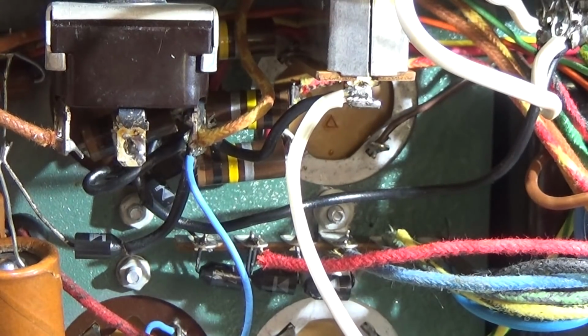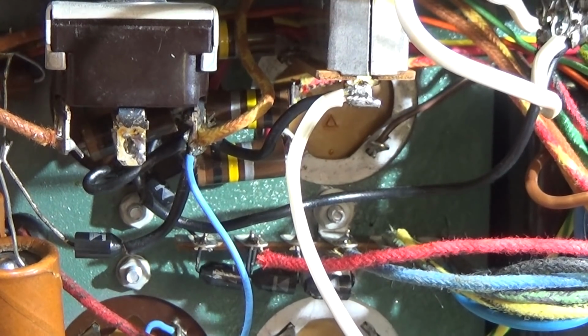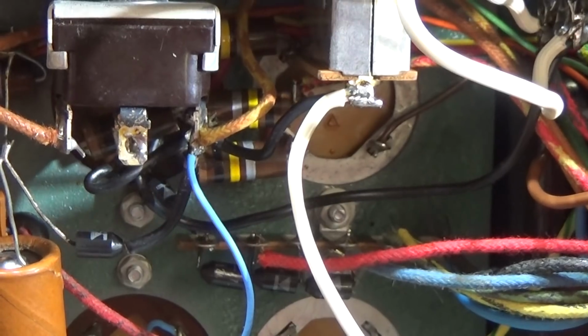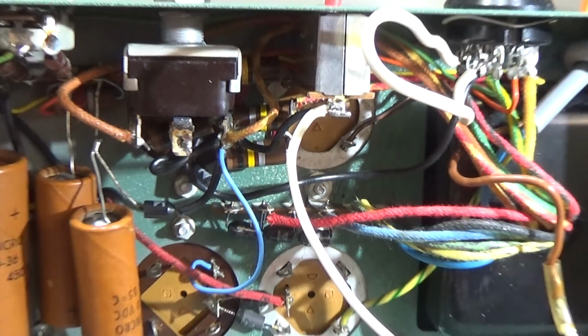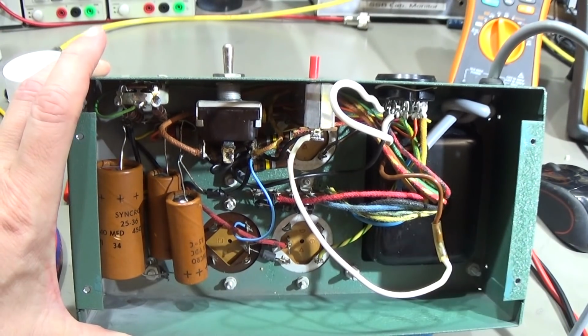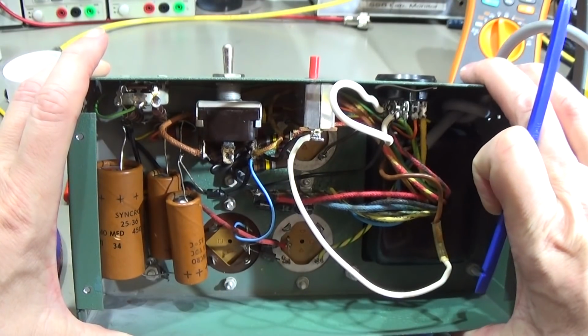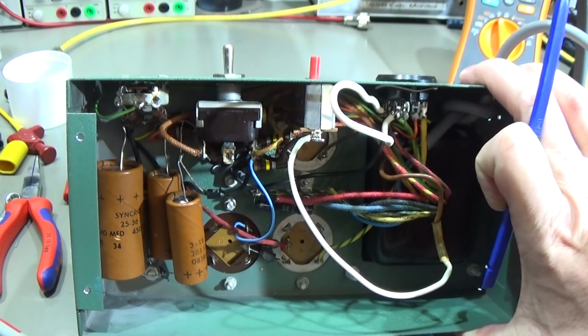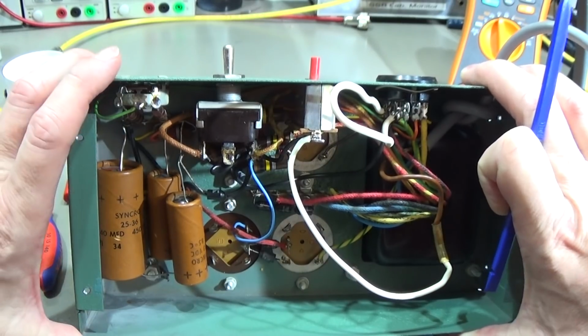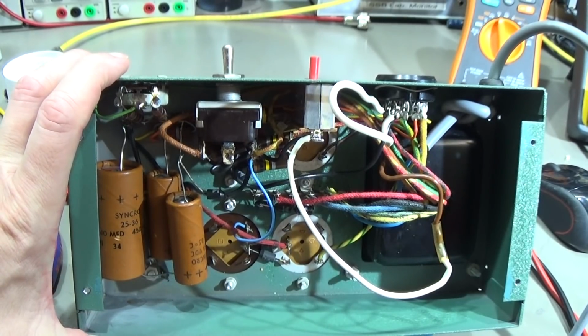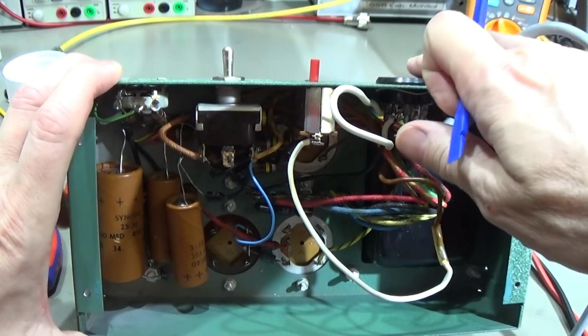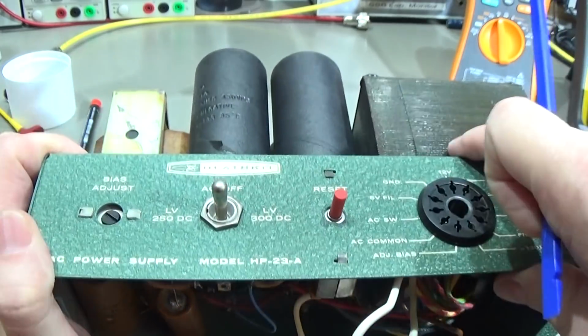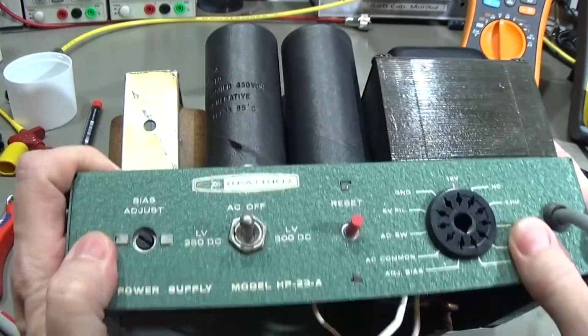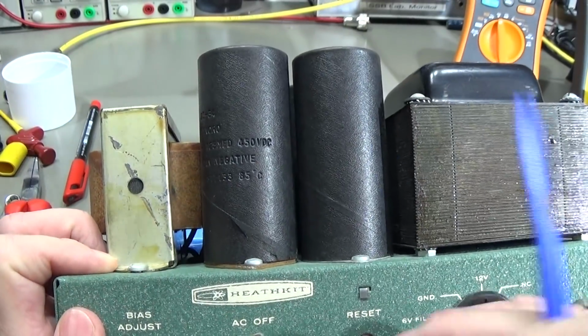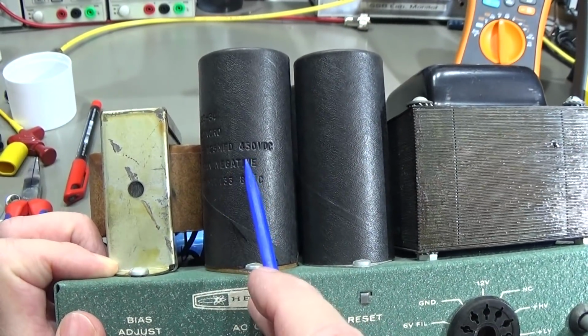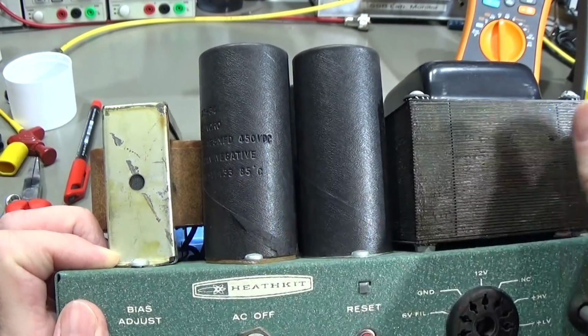Other than that, maybe there is something I have not found yet, but I really do not see another chance than to take it apart, to get down to our capacitors to perform a leakage test on the rated voltages. Therefore we have to disconnect the wires, because if I apply 450 volts to the capacitors here - and we found that these are 450 volt DC capacitors.